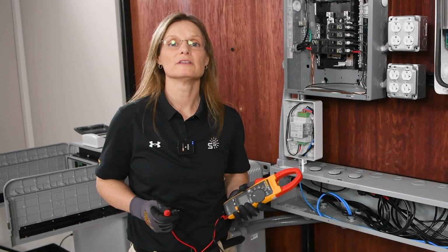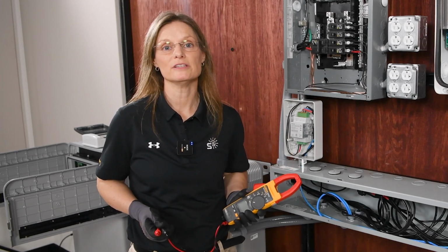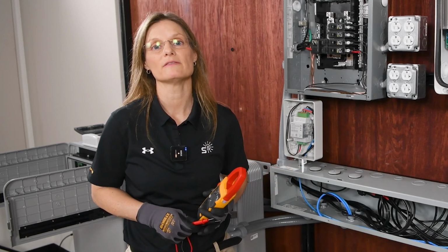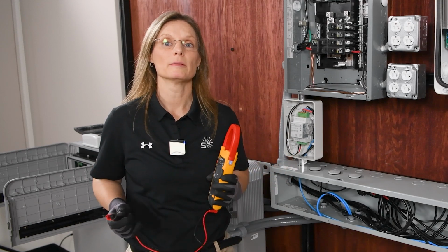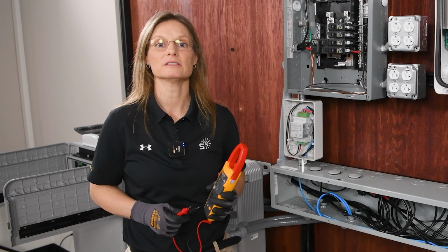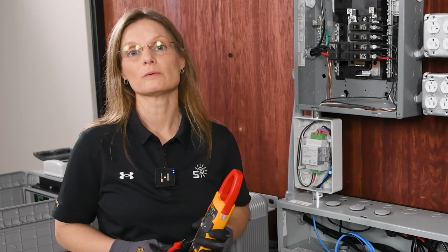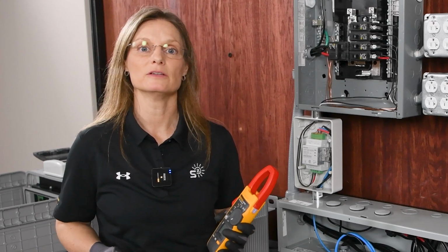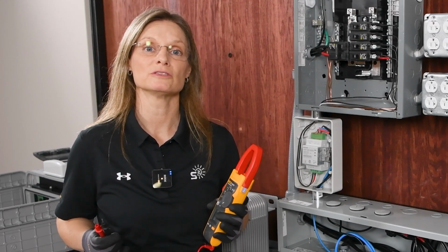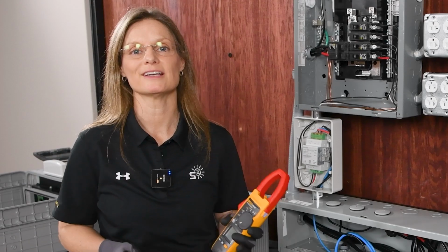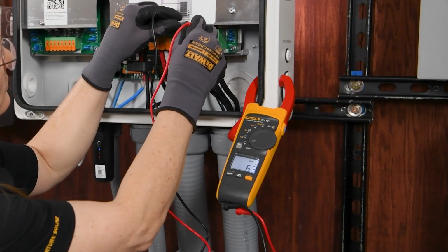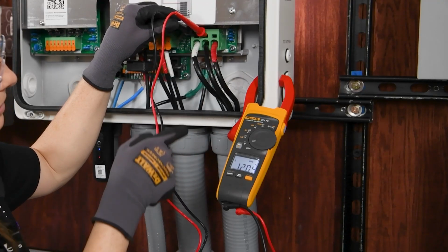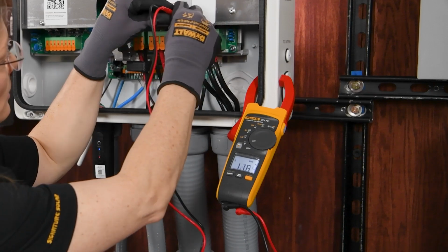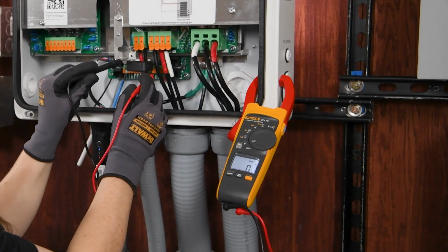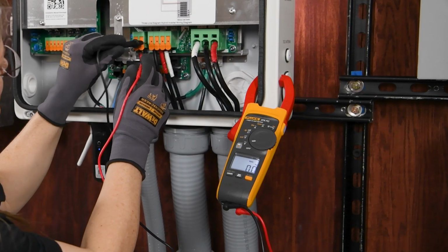Now that we've got everything connected, it's time for our safety checks. We're going to check to make sure that we don't have any cross polarity for our batteries and for our AC connections on our phases. We're going to start with our batteries, to make sure that we have continuity between our positives and that there's no cross polarity between our positives and our negatives. Remember, there is no cross polarity protection on the inverter for the battery, so we really need to make sure that we are checking that to make sure everything is set up correctly.